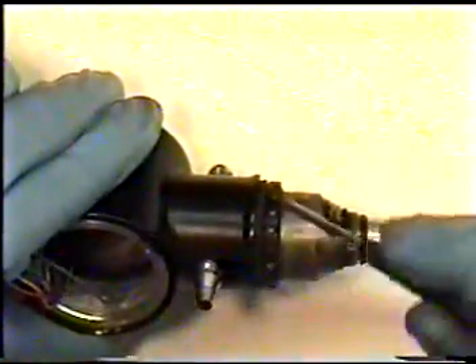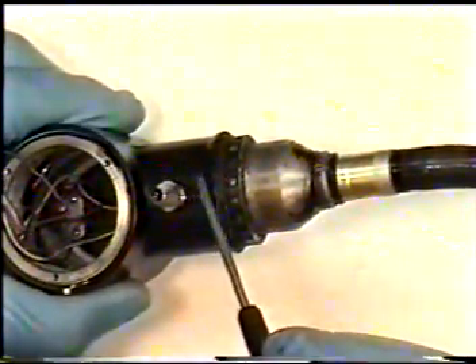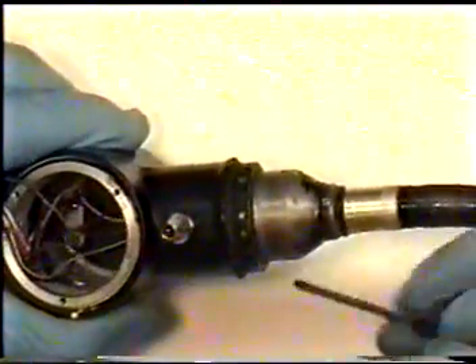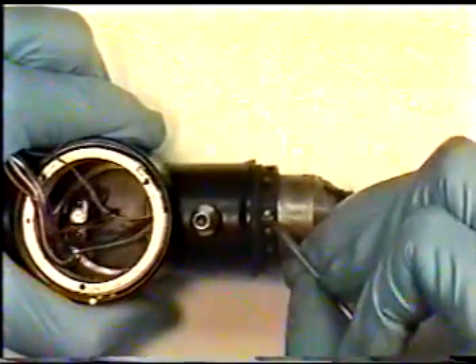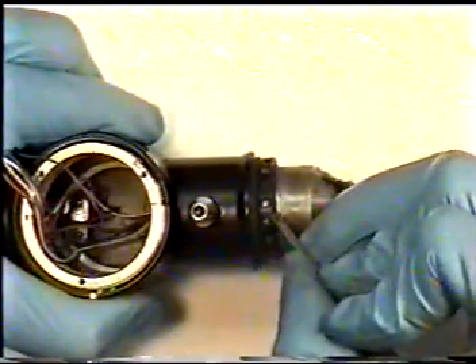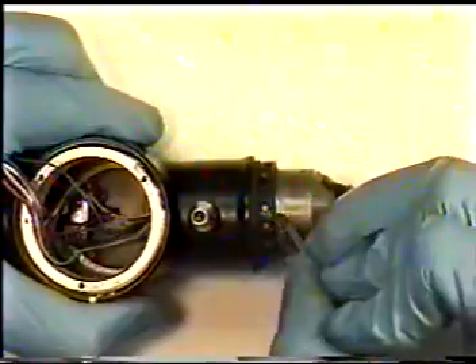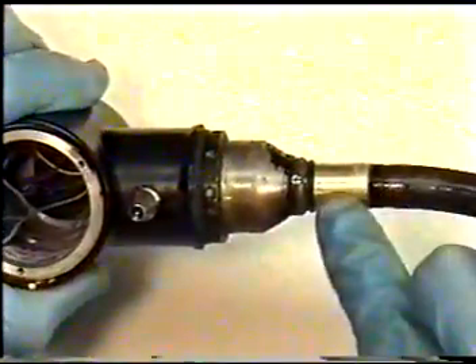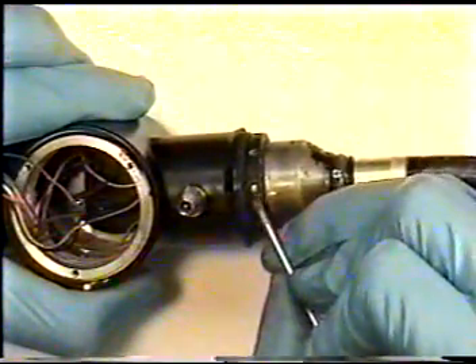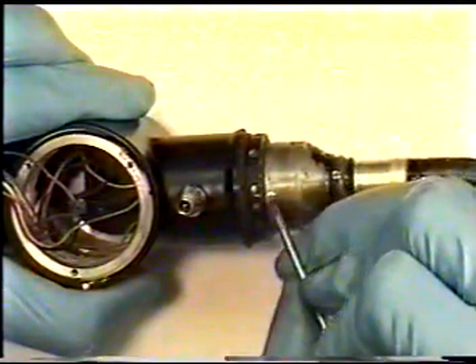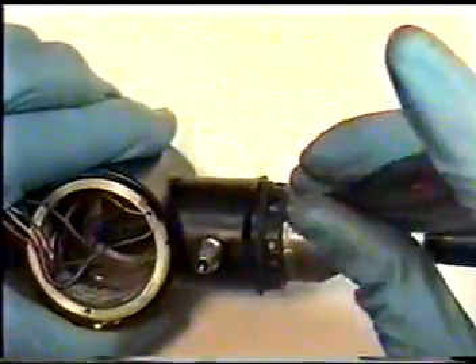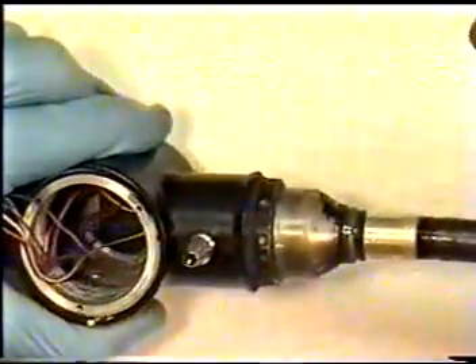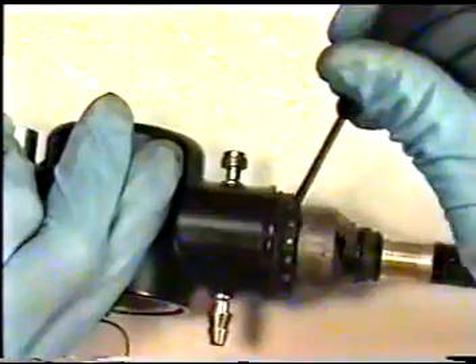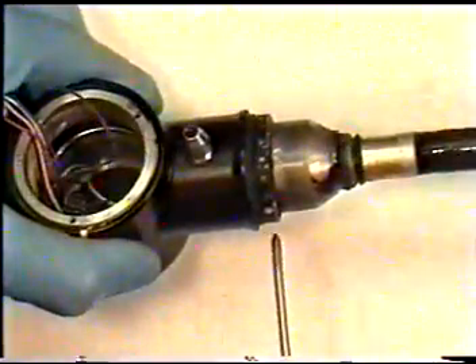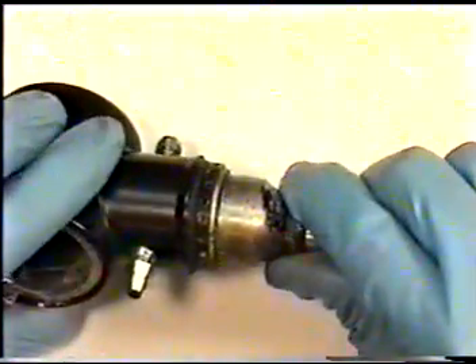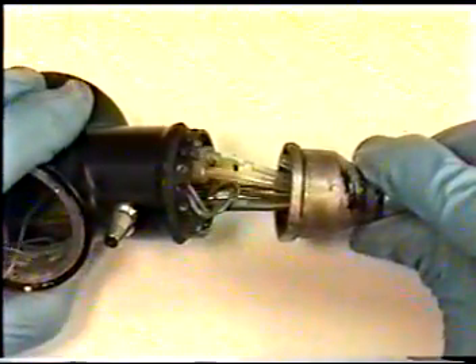Using a Phillips screwdriver, remove 3 screws which hold the connector assembly to your umbilical light guide tube. It is advisable to make a mark with either your Phillips screwdriver or an etching tool in order to reassemble back in the same position so that the connector is not twisted the wrong way. Again, make a small mark, scratching both the connector body and the light guide tube so we can orient this upon reassembly. Once the 3 screws are removed, we can carefully pull out our light guide tube from the connector assembly.